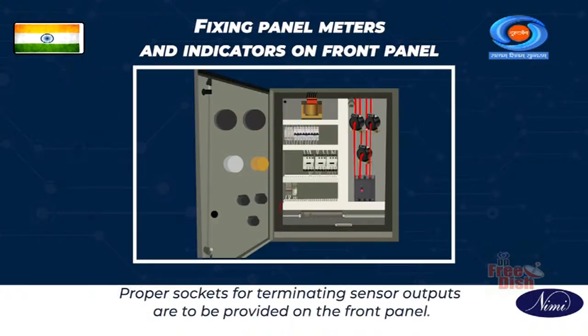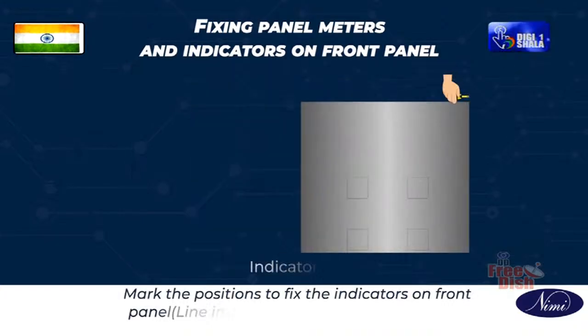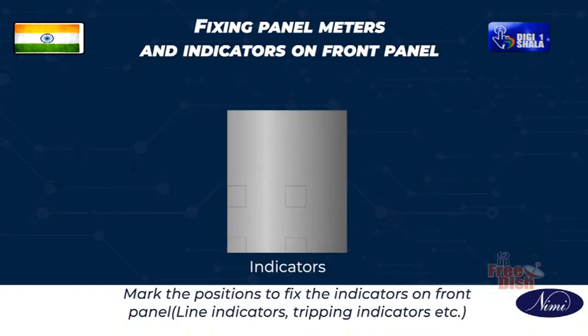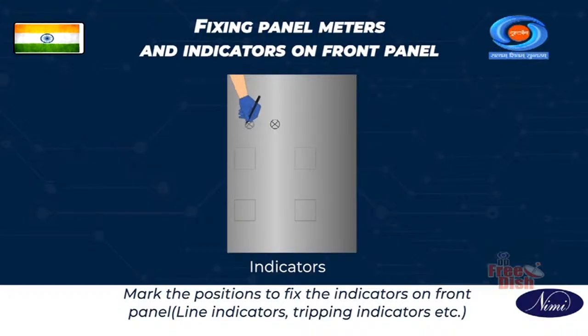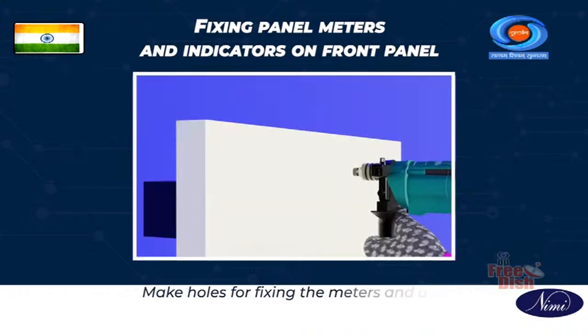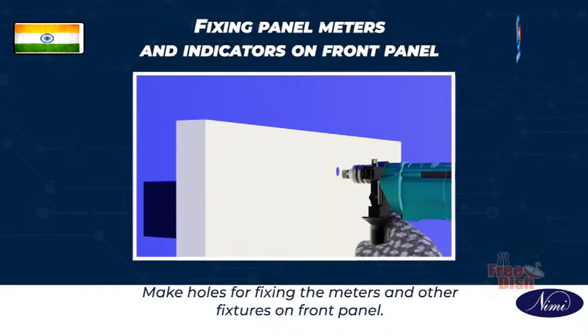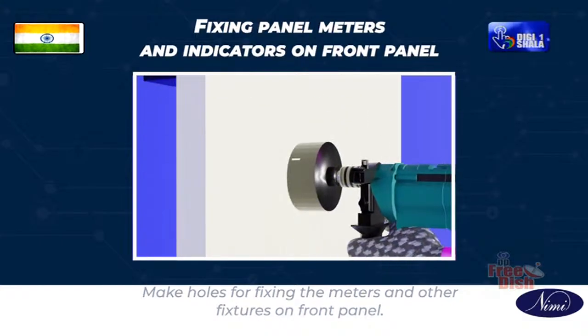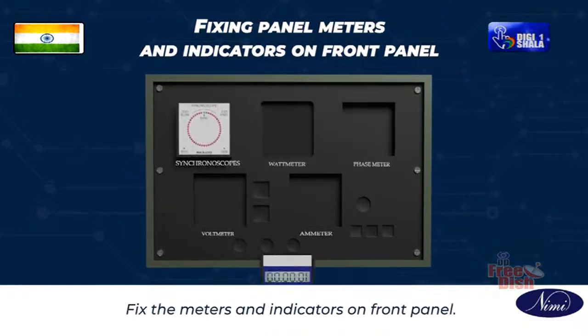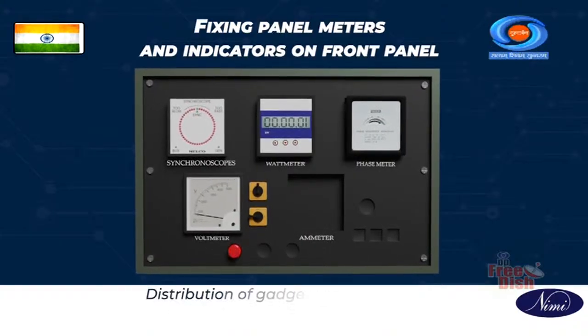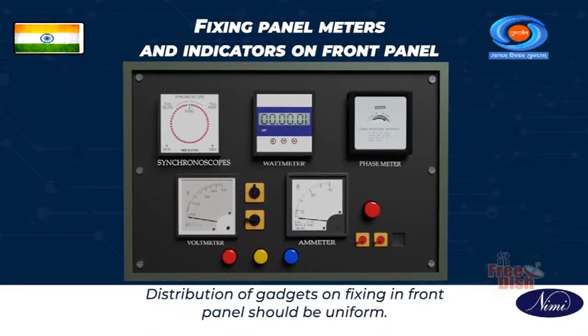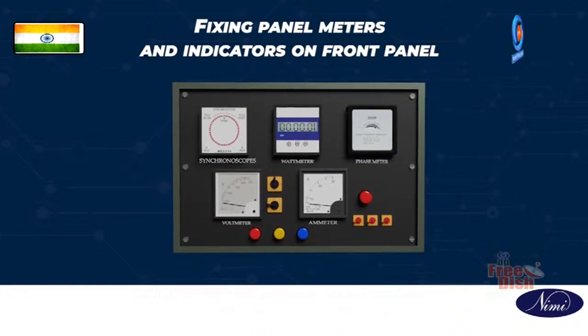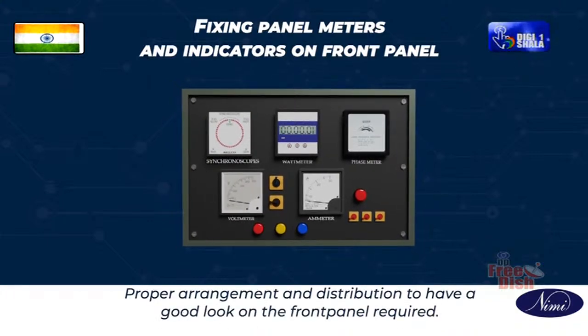Proper sockets for terminating sensor outputs are to be provided on the front panel. Mark the positions to fix the indicators on the front panel, line indicators, tripping indicators, etc. Make holes for fixing the meters and other fixtures on the front panel. Fix the meters and indicators on the front panel. Distribution of gadgets fixed in the front panel should be uniform. Proper arrangement and distribution are required to have a good look on the front panel.